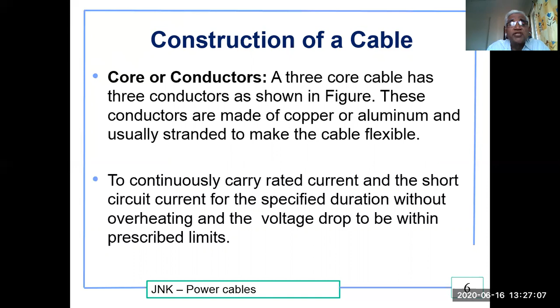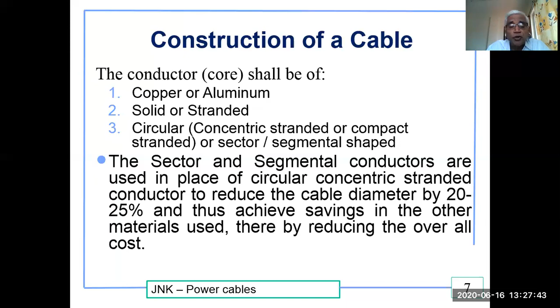Now let us see the conductor, or what we are calling the core. It can be copper or aluminum. It can be solid or stranded. It can be circular, concentric stranded, or compact stranded, or sector or segmental shape, any one of the shapes. The sector and the segmental conductors are used in place of a circular concentric stranded conductor to reduce the cable diameter by around 20 to 25% and thus achieve savings in the other materials used, thereby reducing the overall cost of the cable to the customer.